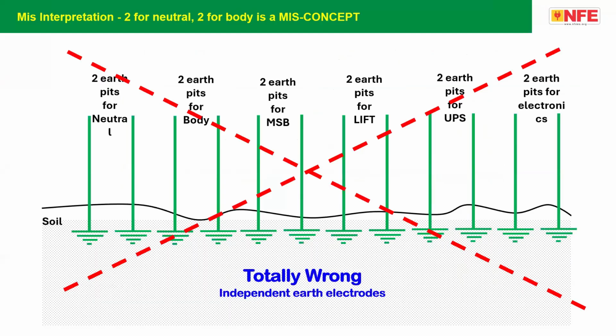This was never written, and it is not scientific. It is never included or explained in any standard. However, a very, very wrong practice we started doing during probably the last 30, 40 years: every transformer, every DG neutral means two separate earth pits, body two separate earth pits, distribution board two separate earth pits, lift separate earth pit. This mistake was predominantly because of the mistakes in the definition, because it was defined that earth means general mass of earth and you have to make a connection to the earth for the immediate dissipation of energy.